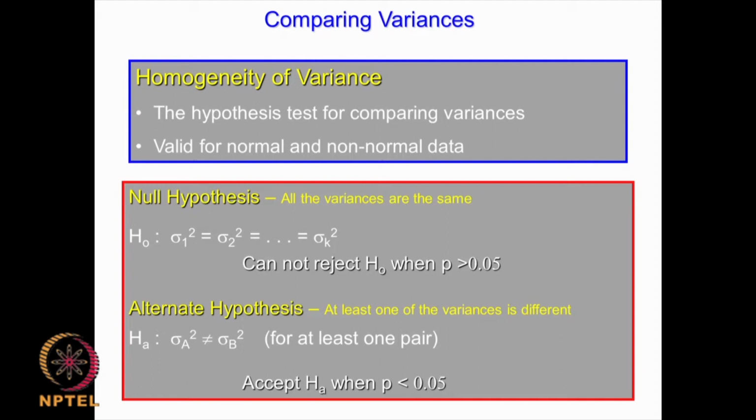The advantage of this variance comparison is that it tells you about the spread of the data, that means the repeatability of the data. Suppose I take an instrument and a sample and I measure it 10 times. I will get some variations or variance. Now, is this variance too much or too little? If I use another instrument and measure the same sample 10 times, I will get another variance. Are these variances very large or very small, acceptable? Here the F test is very useful.